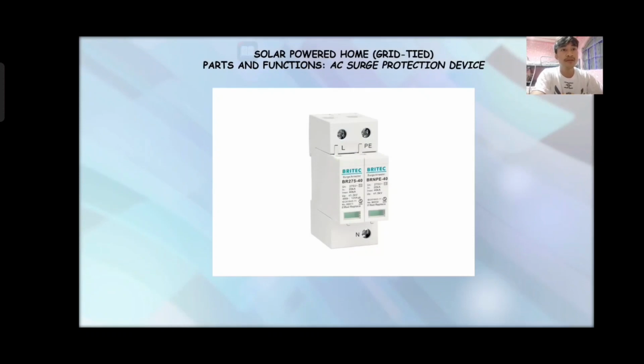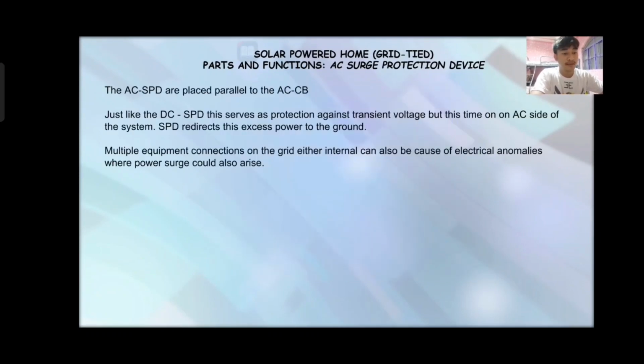Now for the parts and functions of the AC surge protection device. The AC SPD is placed parallel to the AC circuit breaker. Like the DC SPD, it also serves as protection against transient voltage, but this time on the AC side. Multiple equipment connections on the grid, whether internal, can also cause electrical anomalies where power surge could arise. So those are the functions of AC SPD, similar to DC SPD.